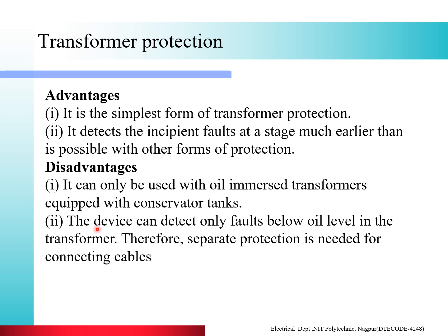Second, the device can detect only faults below the oil level in the transformer. Therefore, separate protection is needed for the connecting cable. The main disadvantage is it can detect the fault only below the oil level. So separate protection for the connecting HT and LT cable is required.